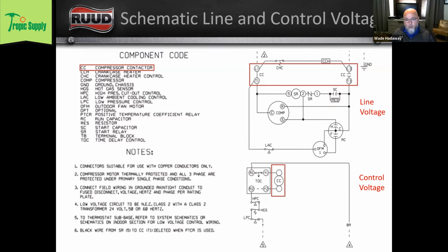So when we energize the contactor coil, when we push 24 volts through the coil on that contactor, it creates an electromagnetic field, so it becomes a magnet, and it pulls the linkage down on our contactor that then closes our L3 to T3 contact.